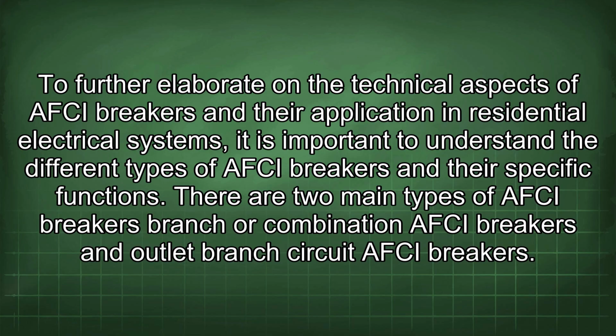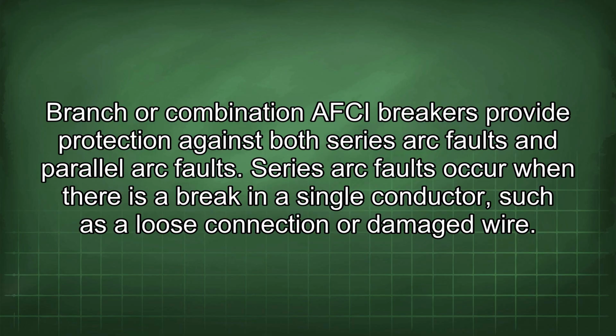To further elaborate on the technical aspects of AFCI breakers and their application in residential electrical systems, it is important to understand the different types of AFCI breakers and their specific functions. There are two main types of AFCI breakers: branch or combination AFCI breakers and outlet branch circuit AFCI breakers. Branch or combination AFCI breakers provide protection against both series arc faults and parallel arc faults. Series arc faults occur when there is a break in a single conductor, such as a loose connection or a damaged wire.